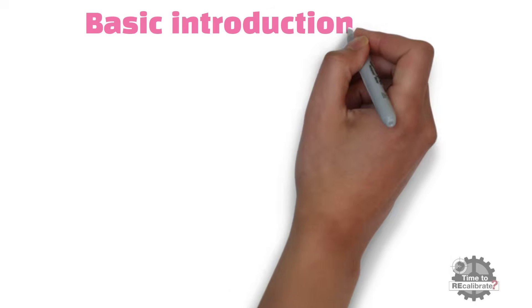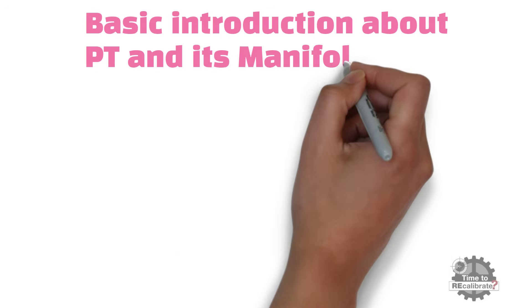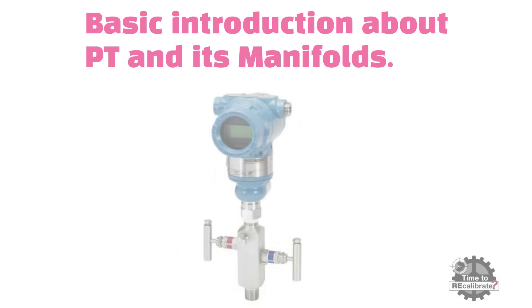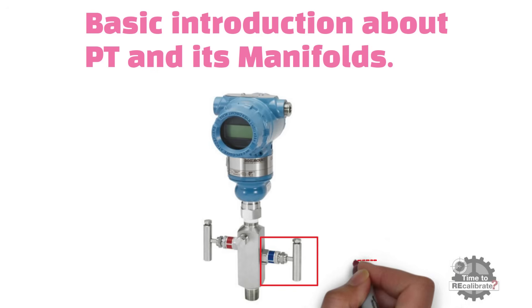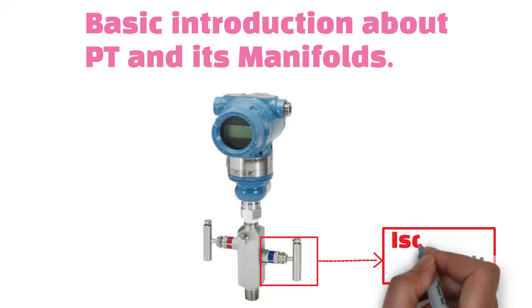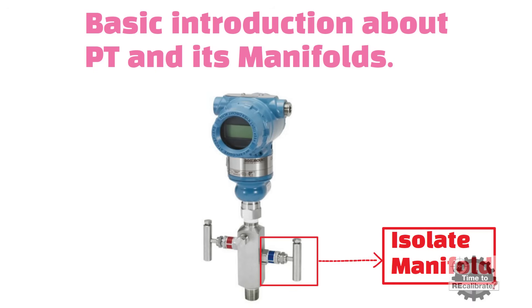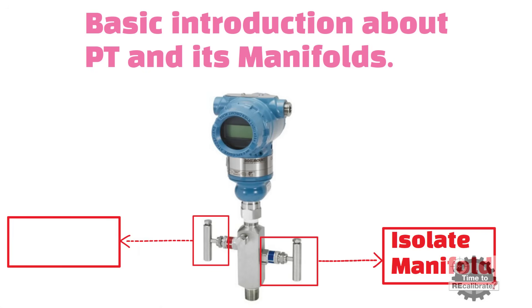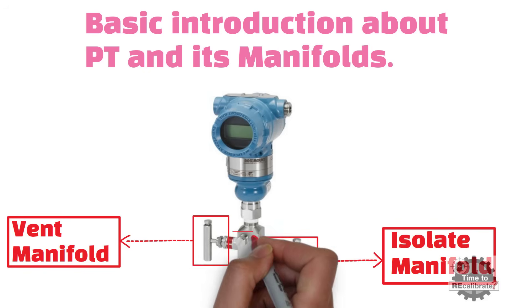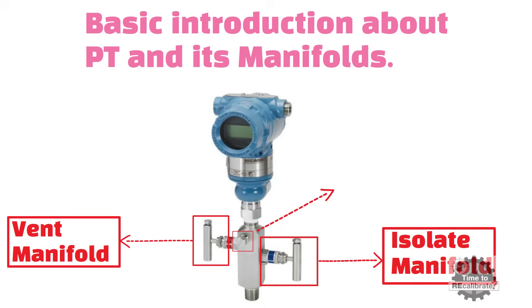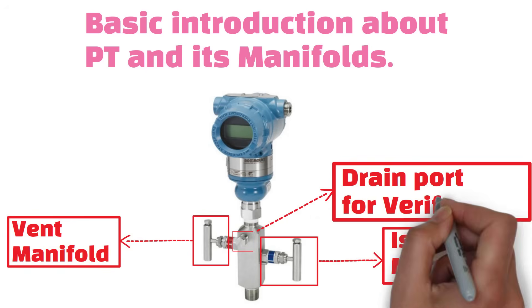Basic introduction about pressure transmitter and its manifolds. All pressure transmitters have two manifolds and one drain port for verification or calibration. The bottom manifold is the isolate manifold, and it remains open in normal operation. The top manifold is the vent manifold and it remains closed during normal operation. The middle port is the drain port and this port is used during verification.